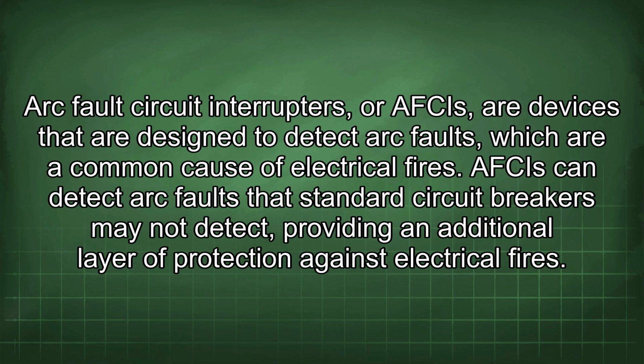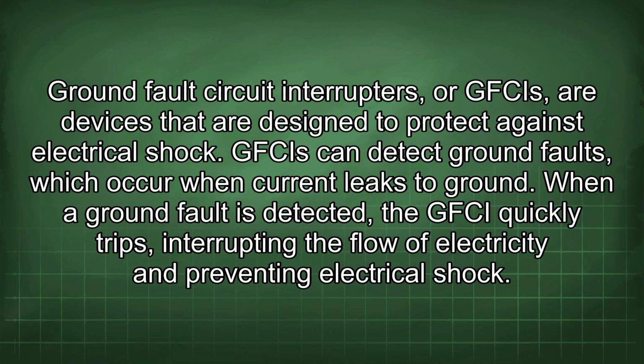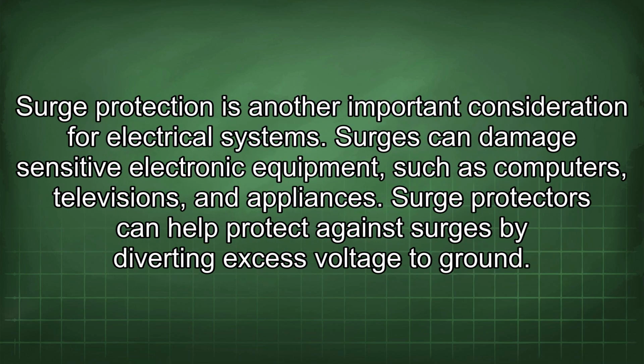Arc fault circuit interrupters, or AFCIs, are devices that are designed to detect arc faults, which are a common cause of electrical fires. AFCIs can detect arc faults that standard circuit breakers may not detect, providing an additional layer of protection against electrical fires. Ground fault circuit interrupters, or GFCIs, are devices that are designed to protect against electrical shock. GFCIs can detect ground faults, which occur when current leaks to ground. When a ground fault is detected, the GFCI quickly trips, interrupting the flow of electricity and preventing electrical shock. Surge protection is another important consideration for electrical systems.